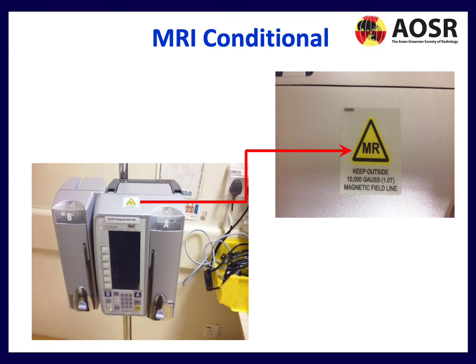Here is where you can find the MRI conditional label. We can see this one here on this monitoring device. Keep outside 10,000 Gauss or the 1.0 T magnetic field line. So there will be warnings on equipment. If there isn't a warning, then you've got to be extra safe. Check with the MRI radiographer.